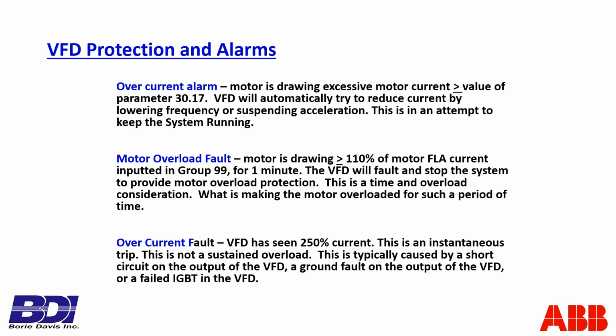The motor overload I talked about briefly, that is a fault that's saying the motor typically has seen 110% current for a minute. The VFD will fault and stop the system to protect the motor from burning up. This is a time overload. This isn't something that just, bang, happens. This is typically like a bearing wearing out, as I mentioned earlier, which starts to increase the load on the system and eventually makes it no longer in the design of the system. The protection has shut you down, but it's telling you, you better go look at the motor's load.